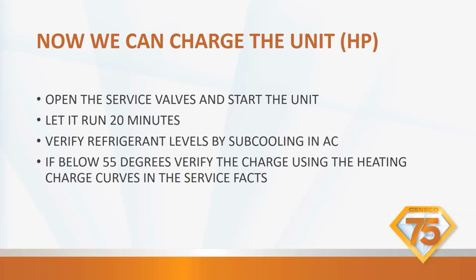Okay, the reason we need subcooling is so that we have 100% liquid at the orifice or the TXV when it goes to regulate the refrigerant through the orifice. Okay, we need 100% liquid refrigerant there. As it goes through your TXV or your orifice, it's going to be a liquid changing to a gas.